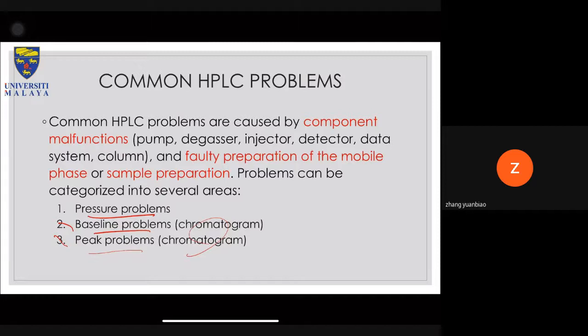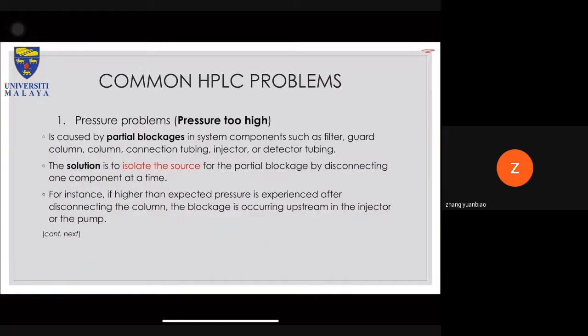Okay, so for the first category, pressure problem, say the pressure is too high, so what might be the issue? It might be caused by partial blockage of a system component, such as the filter, the guard column, the column itself, the tubing, injector, or the detector. Okay, and based on my experience of more than 10 years of using HPLC, now that it's 2021, the most common problem when pressure is too high comes from the filter and guard column. So those are the most common ones.